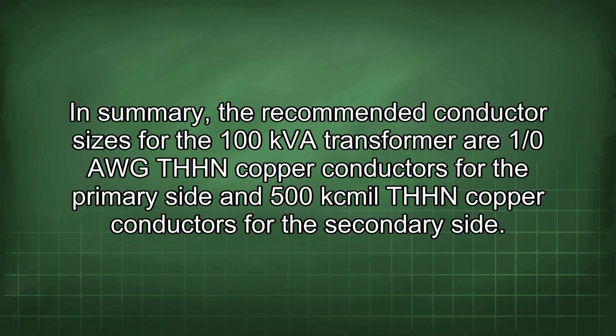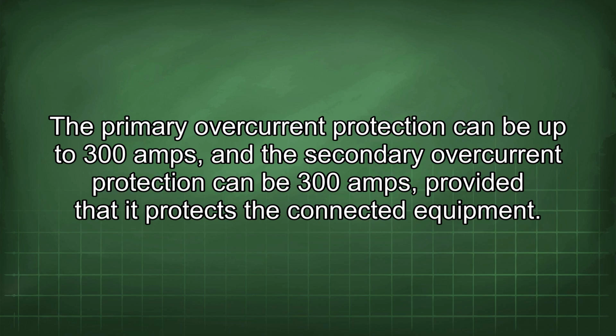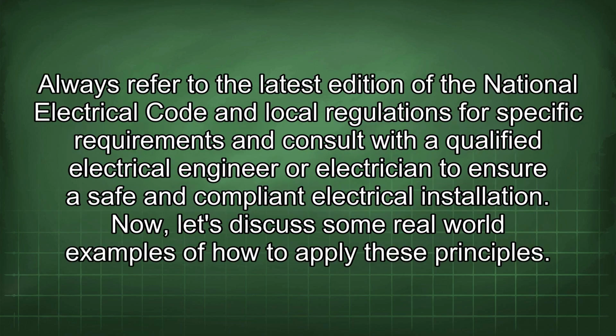In summary, the recommended conductor sizes for the 100 kVA transformer are 1/0 AWG-THHN copper conductors for the primary side and 500 kcmil-THHN copper conductors for the secondary side. The primary overcurrent protection can be up to 300 amps, and the secondary overcurrent protection can be 300 amps, provided that it protects the connected equipment. Always refer to the latest edition of the National Electrical Code and local regulations for specific requirements, and consult with a qualified electrical engineer or electrician to ensure safe and compliant electrical installation.